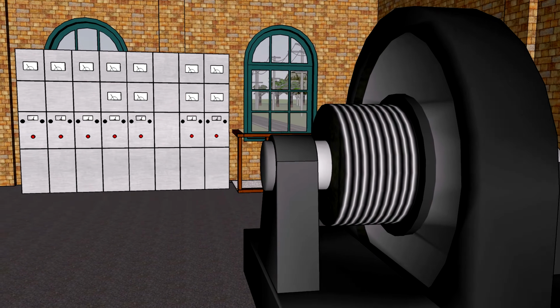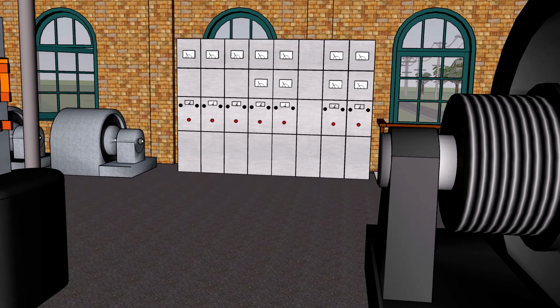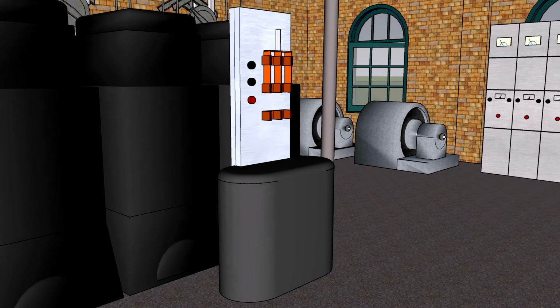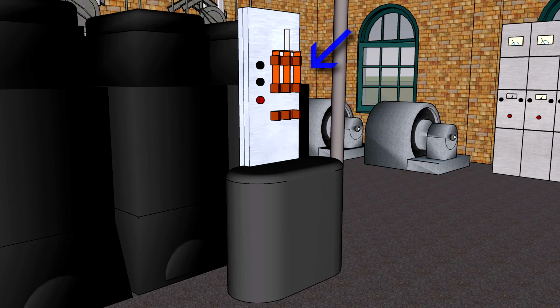Positioned in front of the transformers was 1 or sometimes 2 75 kilowatt reactive coils, recognizable by their rounded corners and the top control panel with a large retro knife switch. The reactive coils helped with the regulation of the line voltage between the transformers and the rotary converters by synchronizing the oscillating current, and the panel mounted on top was used for starting the rotary converter. Wiring for this reactive coil and starting panel came through an opening in the concrete floor, where it was again cooled by the positive flow of basement air.